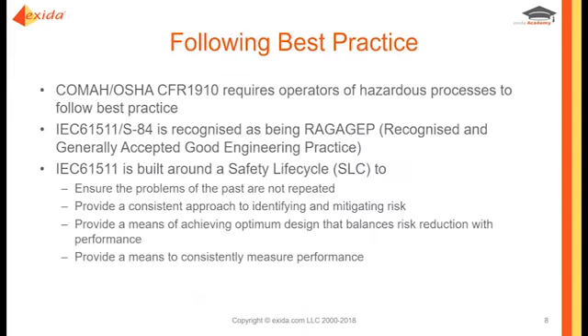First thing managers need to know, especially if working for an organization that comes under COMAH in the UK, or OSHA in the US: this requires operators of hazardous processes to follow best practice. So what is best practice? Often called RAGAGEP in the past—recognized and generally accepted good engineering practice. This relates to IEC 61511 for the process industries, whereby this is recognized as being best practice.